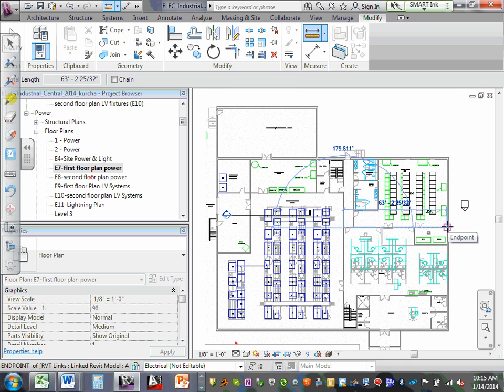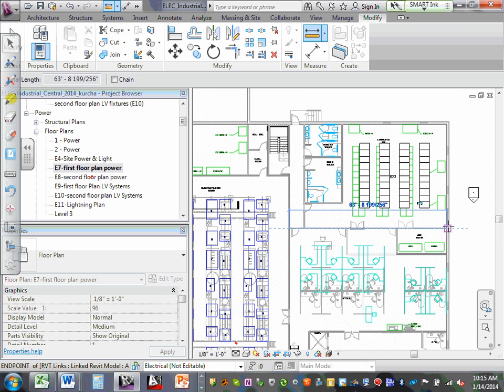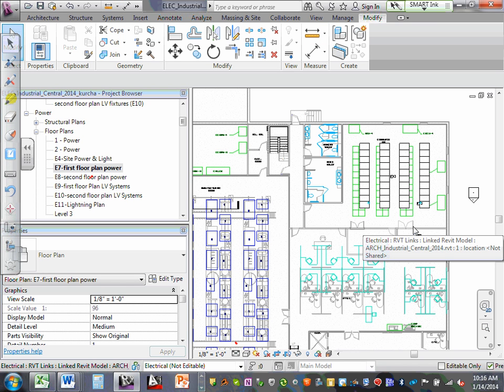And then if you look at, let's say this office area, typically we ceiling mount these devices. A strobe rated at 100 candela, which is the light intensity of that strobe device, the visual device, has a coverage of 50 feet by 50 feet. If it's on the wall, it's 50 feet out, away from the wall, on axis, and then 25 feet that direction and 25 feet that direction for a total of 50 feet. Okay? What I would do is I'd lay this thing out, keeping in mind that we want to visually notify everybody in the building.